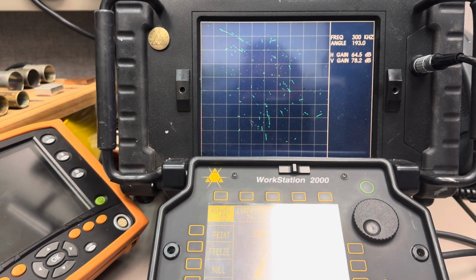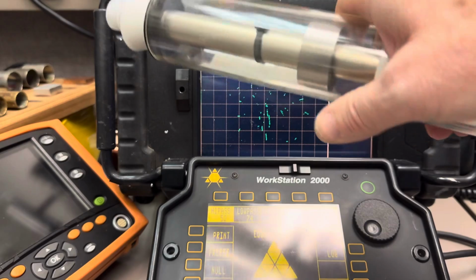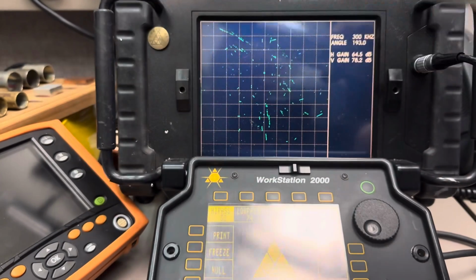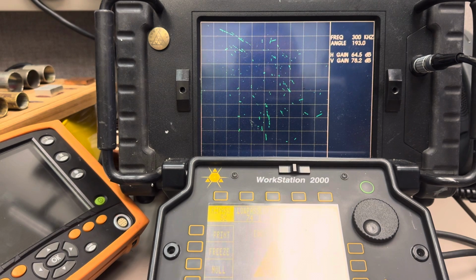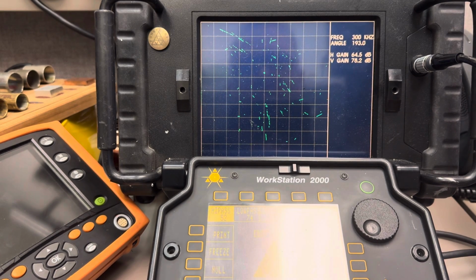Well, instead of having a cal block with holes in it, you'll have a calibration tube that's loaded with different types of flaws. Now, if you're doing a big inspection and there's multiple types of degradation based on your degradation assessment, and that's a document that says what are the most likely damage mechanisms that you're going to encounter. So what you expect to find and what you could find based on operating experience for other similar types of heat exchangers.